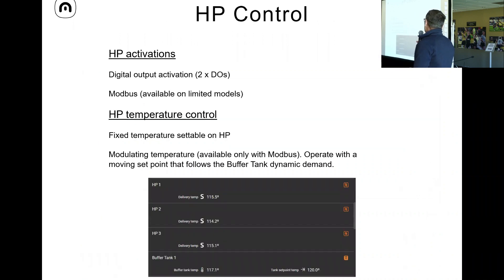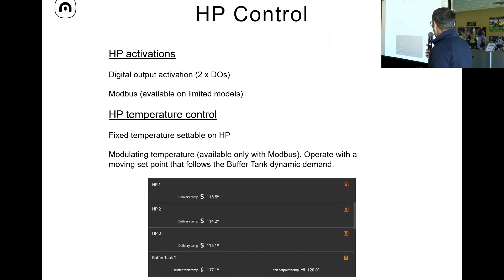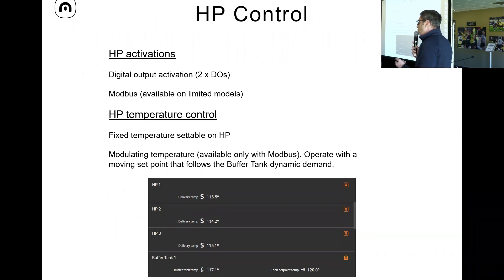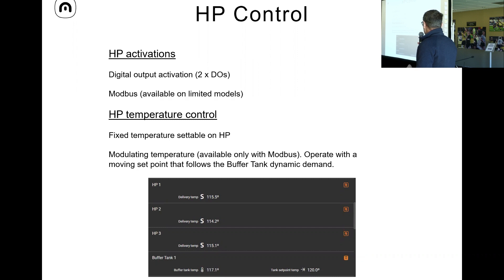There are different ways to control a heat pump. Here with the water, we decided to go with the Modbus strategy — the heat pump is integrated in our controller via Modbus, meaning we can communicate with the heat pump and dictate what temperature we want based on the buffer tank and that delta T. The modulating temperature is only available through Modbus.